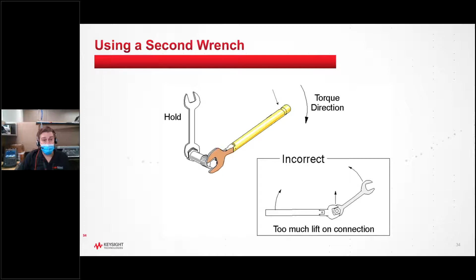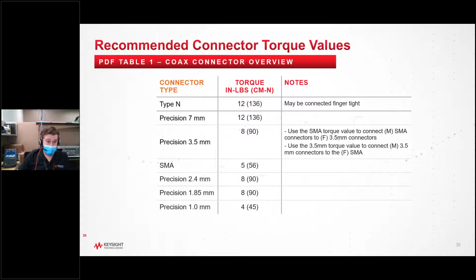Here are the common torque values, but you'll just have to look this up for your specific situation based on your connector type. And just want to point out that the torque value for an SMA is actually lower than the torque value for a 3.5, even though sometimes they're used interchangeably. And the reason is that too much torque on an SMA can actually damage or make a poor connection. We'll jump through that. And this becomes increasingly important when you're in 1mm connectors because they're easy to break and way more expensive. So we'll sum it up real quick because we have a lot more to get to.